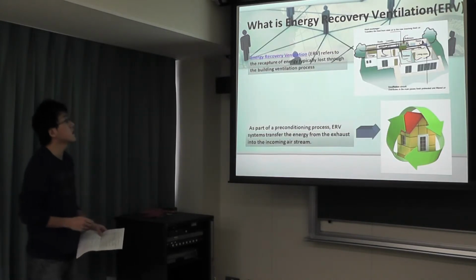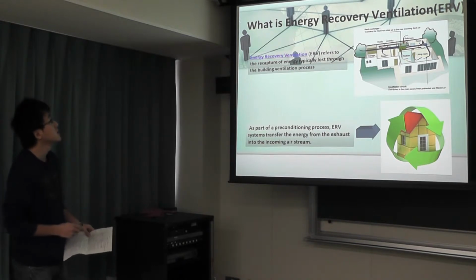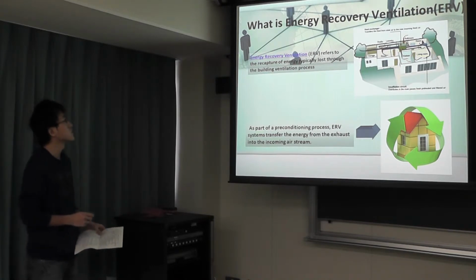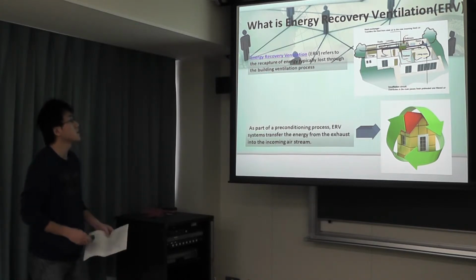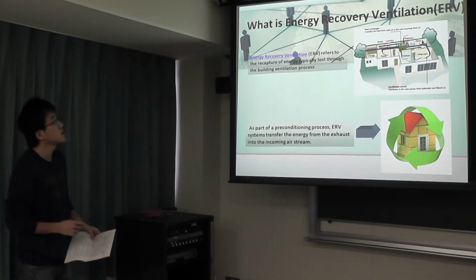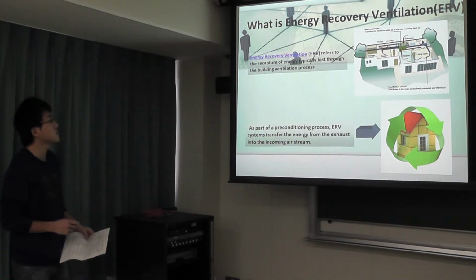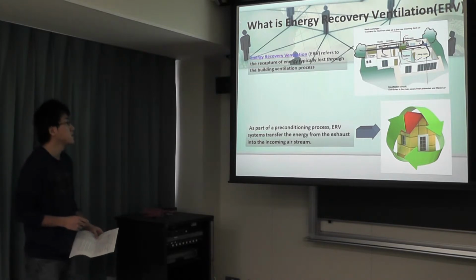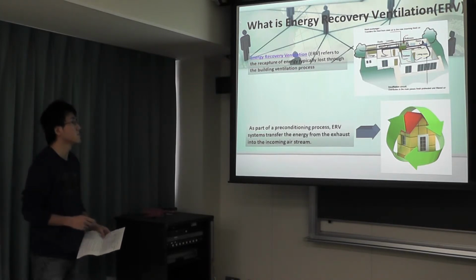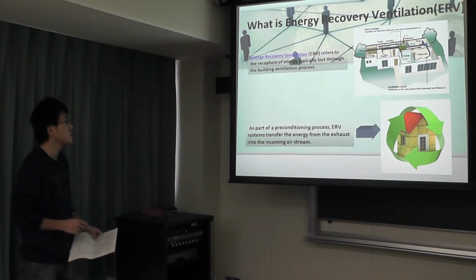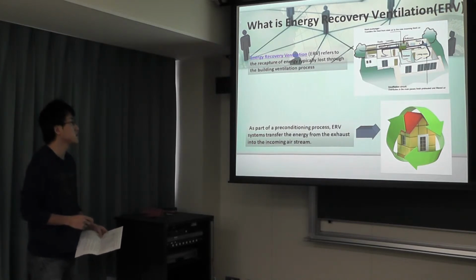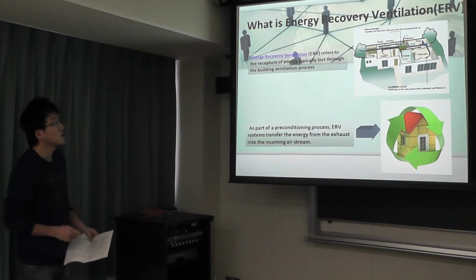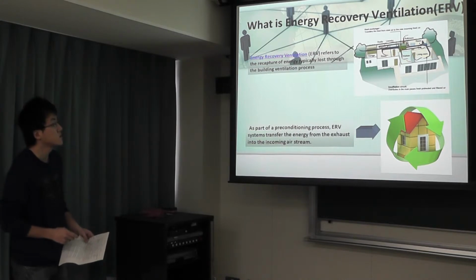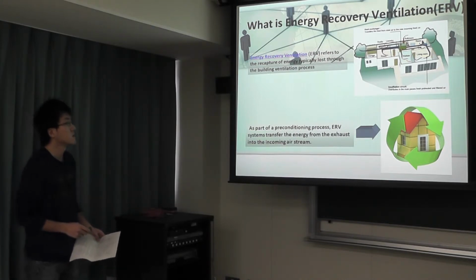What is energy recovery ventilation? Energy recovery ventilation refers to the recapture of energy typically lost through the building ventilation process. As part of a preconditioning process, ERV systems transfer the energy from the exhaust into the incoming air stream. ERV is like a greenhouse to protect the energy.